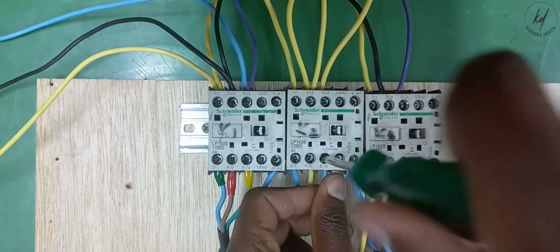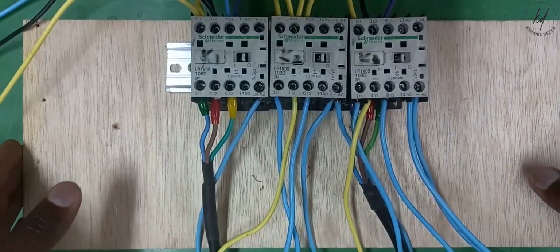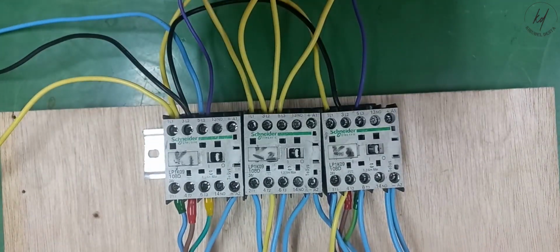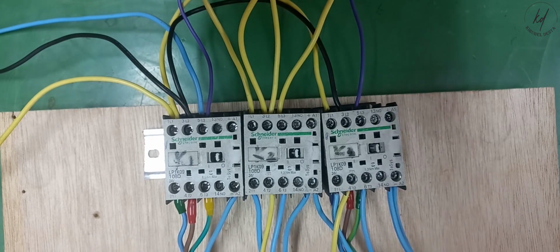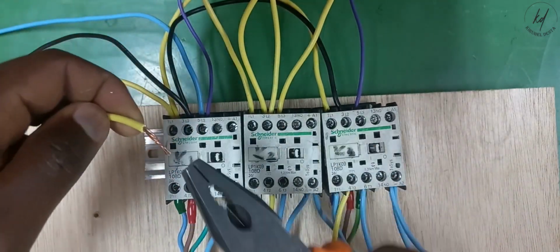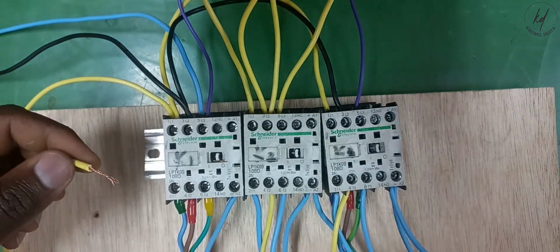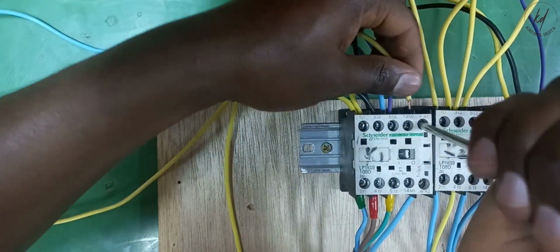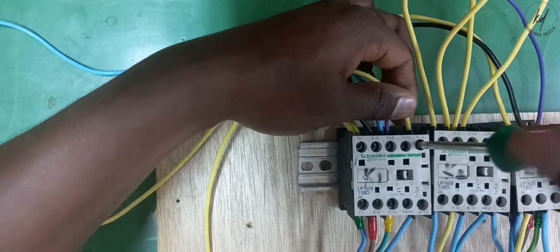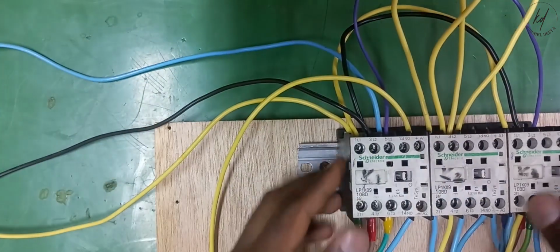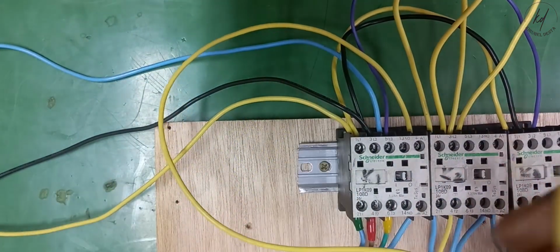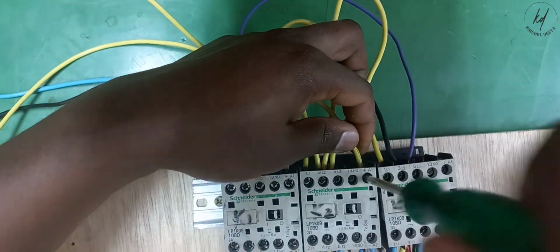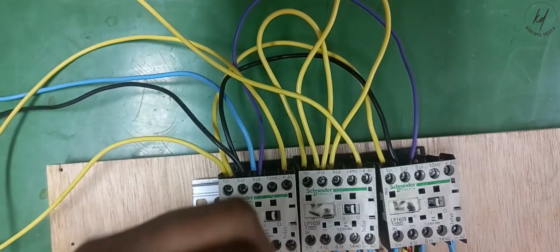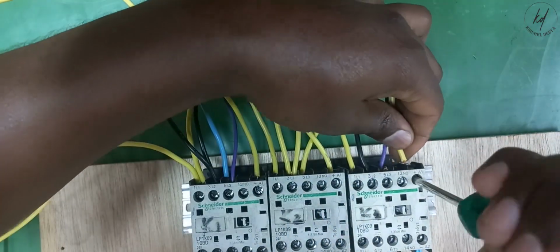Contactors can break current over a wide range, from a few amperes to thousands of amperes, and voltages from 24-volt DC to thousands of volts. In addition, these electrical devices come in varying sizes, from handheld dimensions to approximately a meter or yard on one side. The most common application area of the contactor is high current load. Contactors are known for their capability to handle currents of over 5,000 amperes and high power over 100 kilowatts. Heavy motor currents produce arcs when being interrupted. These arcs can be reduced and controlled using a contactor.